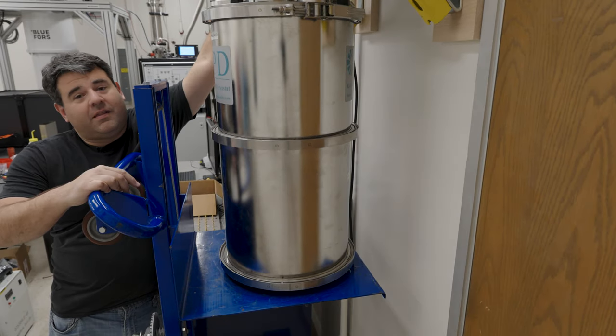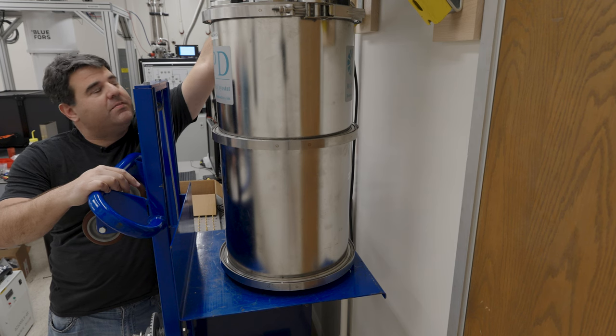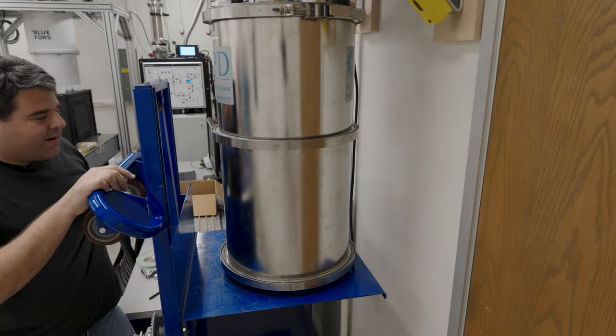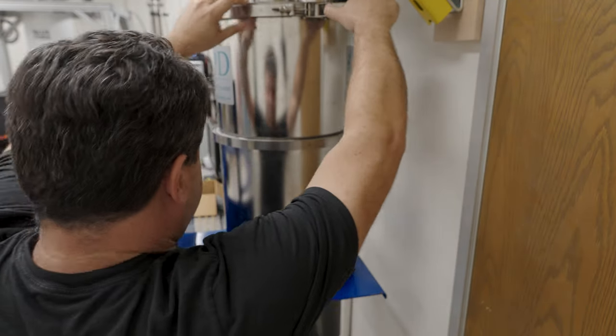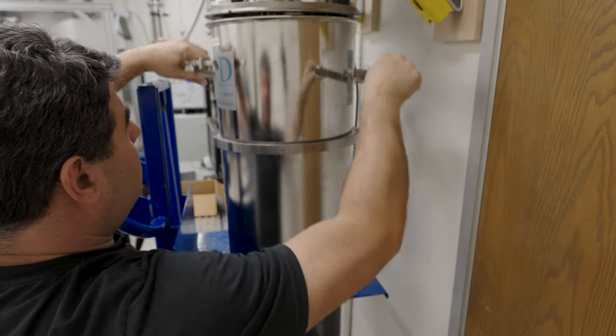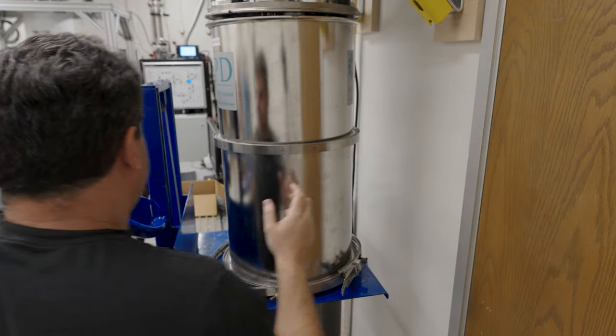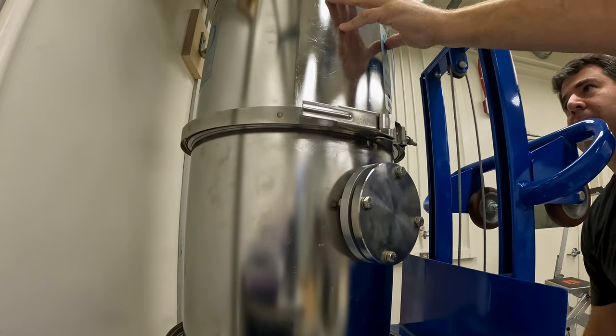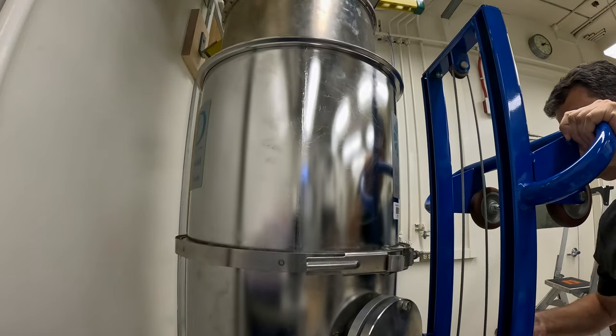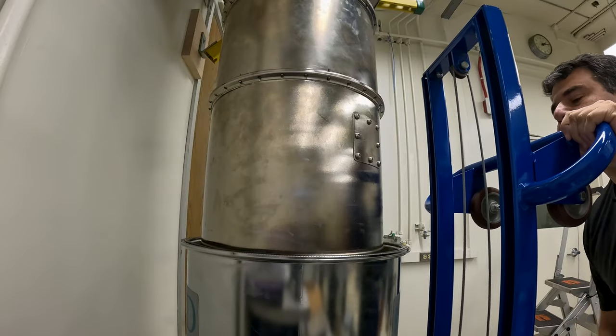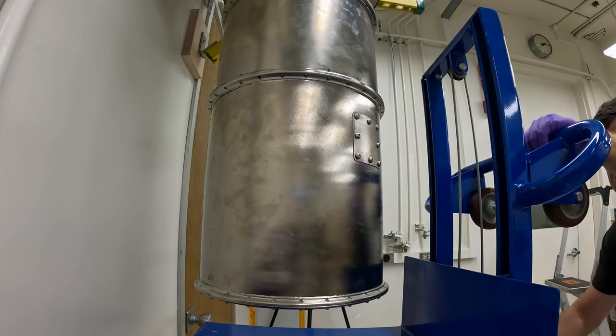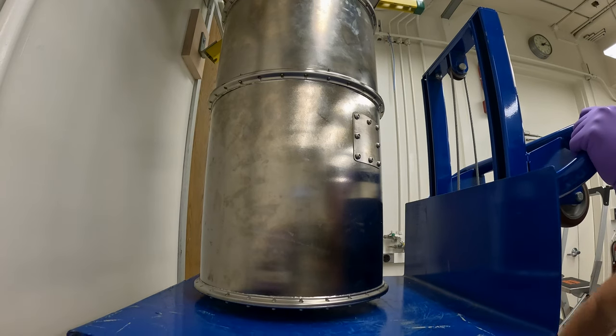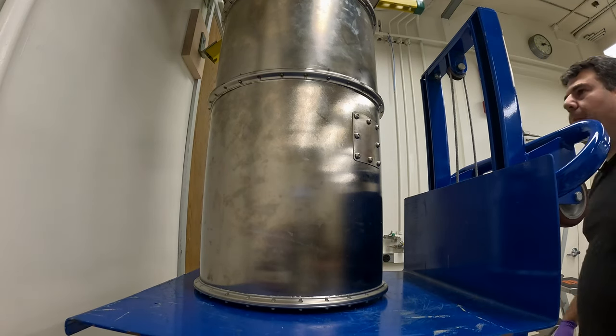So the first thing we got to do is break the vacuum and then drop the shields just like on the previous fridge. Unlike the previous fridge, this fridge is not under vacuum. So looks like this one was left with air in it. Shouldn't be a problem though.